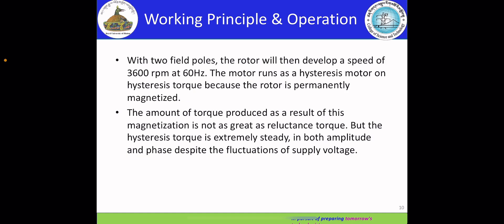As the rotor approaches synchronous speed, the frequency of the current reversal in the rotor bars decreases and the rotor becomes permanently magnetized in one direction as a result of the high retentivity of the steel rotor. With two poles, the rotor will develop a speed of 3600 RPM at a frequency of 60 Hz. The motor runs on hysteresis torque because it is permanently magnetized. The hysteresis torque is extremely steady in both amplitude and phase despite fluctuations of the supply voltage.